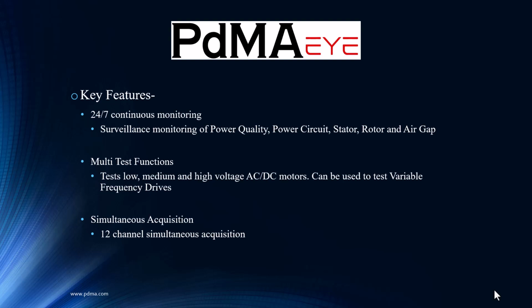Exactly, low frequency drives, which tend to cut off the... so what you're saying is you can actually put transducers in now instead of the regular CTs that go out with an MTAP. A big step with the PdMA EYE is now we can get down to that zero hertz, a very low frequency, with actual transducers. Transducers can be the 4 to 20 milliamp, the 0 to 10 volt type. There's just a variety of transducers out there depending on what you're measuring.